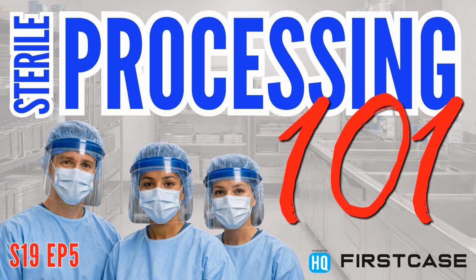What happens if an instrument goes into the sterilizer that still has something on it? Well, very practically, Melanie, I guess I'll turn the question around and ask you, the OR nurse in the room, practically what happens when that happens? Right, the instruments are flung across the room, the room gets torn down, right? So the reason that creates such a hullabaloo in the OR is because you now have doubt or question of whether or not the instrument is sterile. So that debris on the instrument, the line of reasoning goes that that debris could shield that portion of the instrument from getting contact from the sterilant, whatever sterilant you're using. And so underneath that dirt and debris could be some existing and living microbial life. And so we reject it as if it's pathogenic, even though we don't really know.